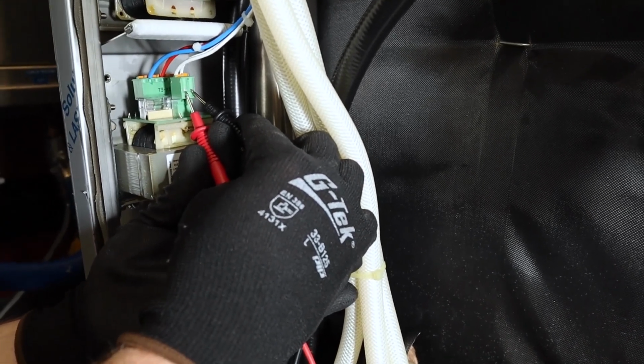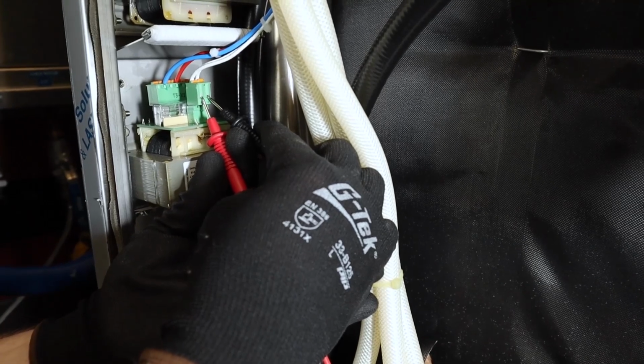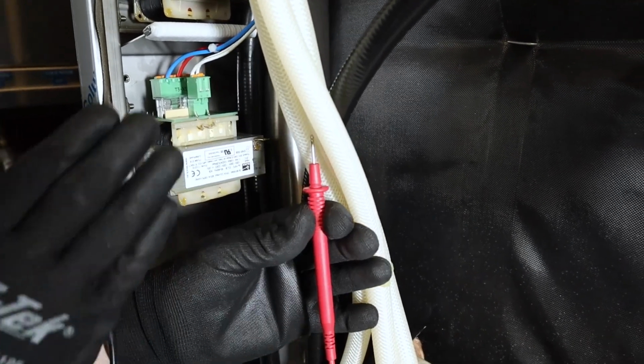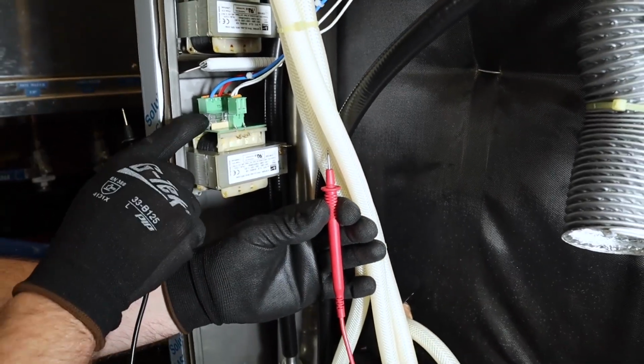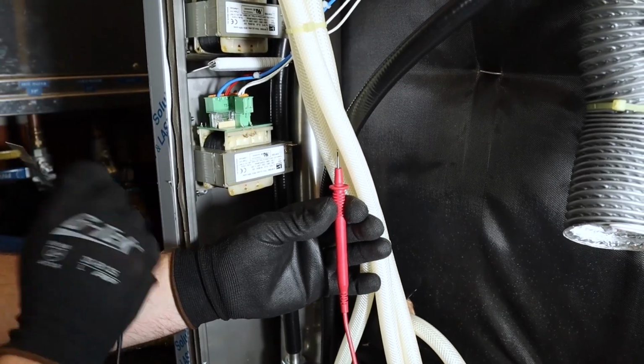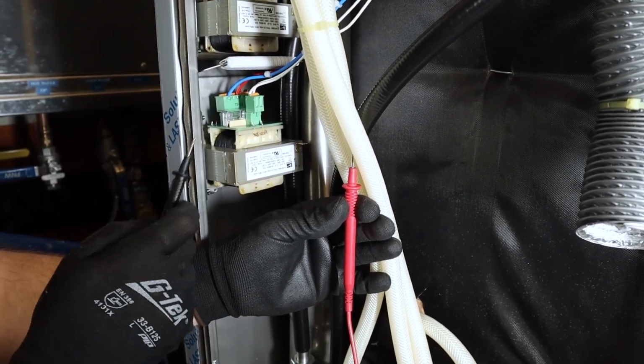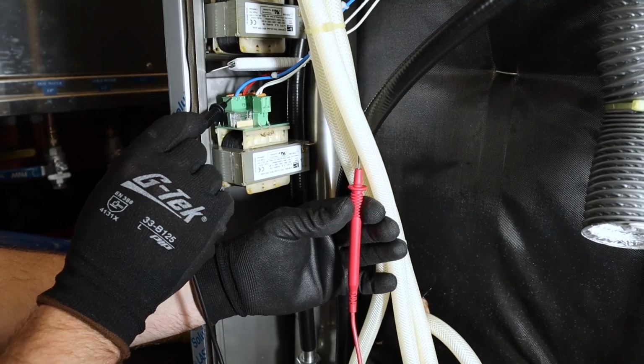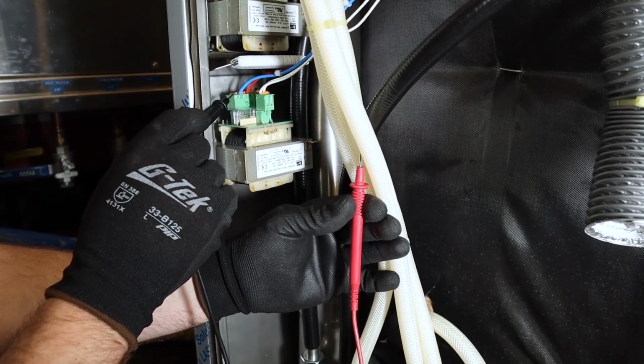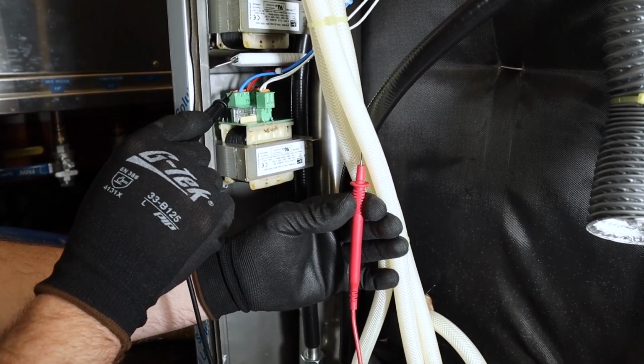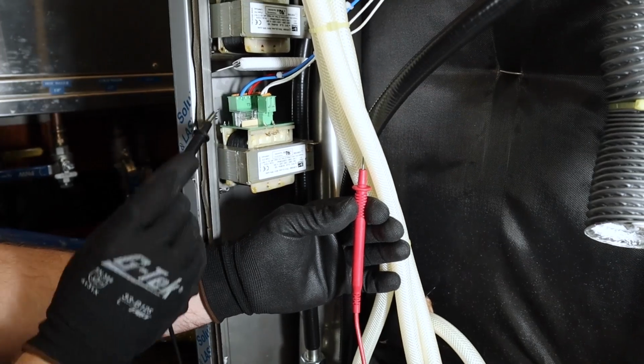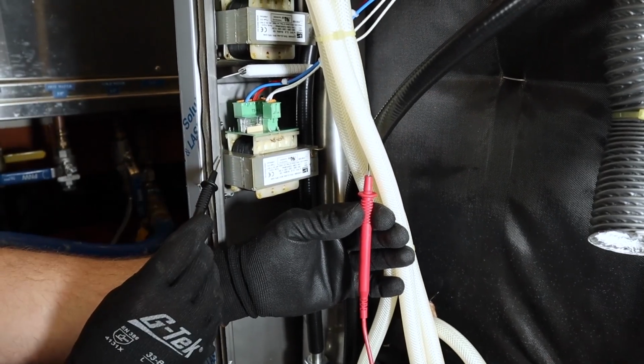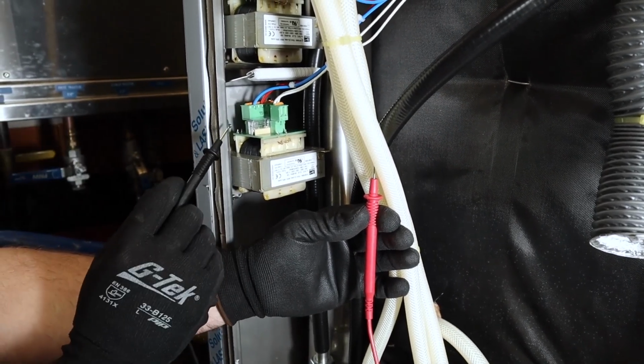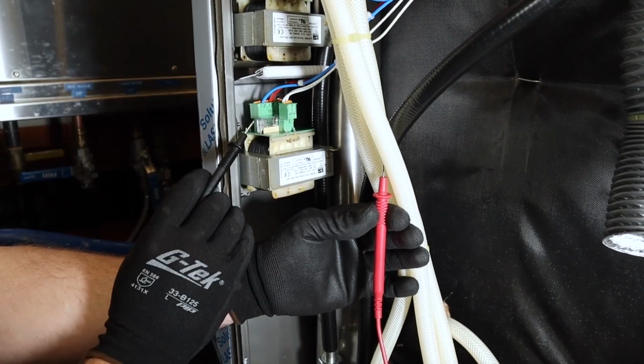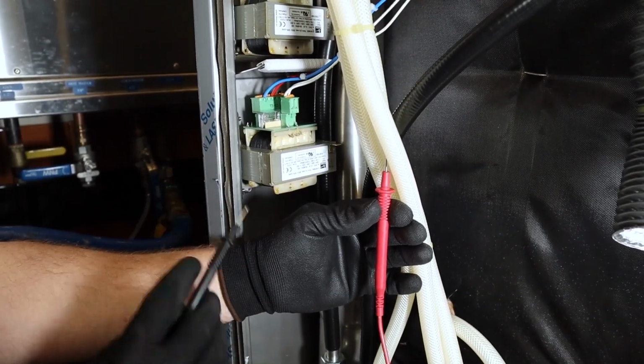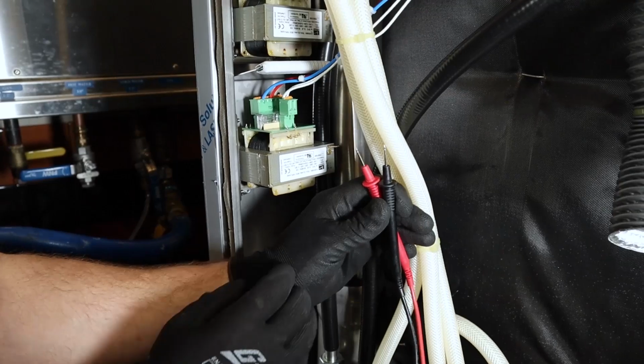Now let's say we were not getting it at all, and we were never getting ignition. It might be a bad transformer, but it also might be a bad fuse right here on top of the transformer. So keep that in mind. Now that's assuming that we have our line voltage back here at this connector, which comes from our ignition module. So we would want to verify that we have our line voltage back here on this connector. And if we did, and we didn't have it coming out right here, then we could have a bad fuse or possibly a bad transformer. So that's how we would check our voltage.